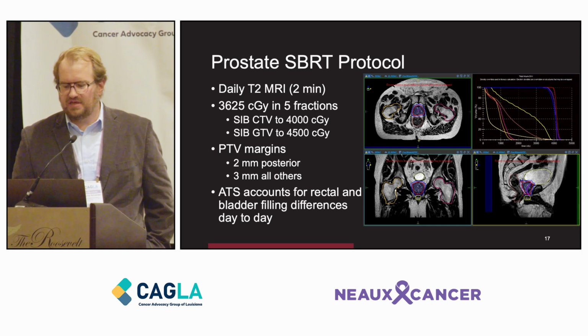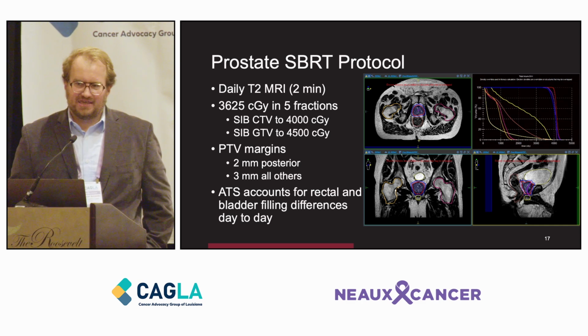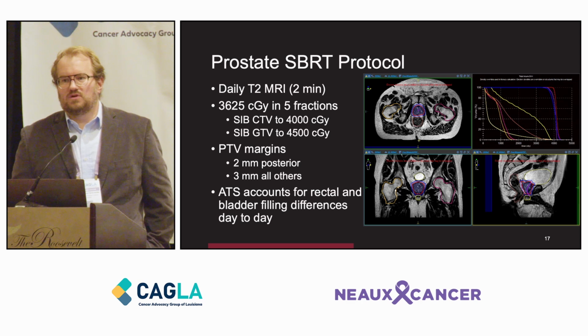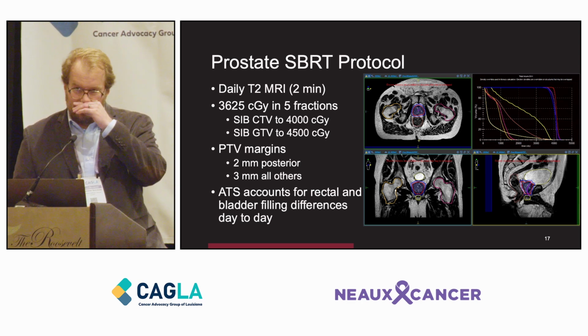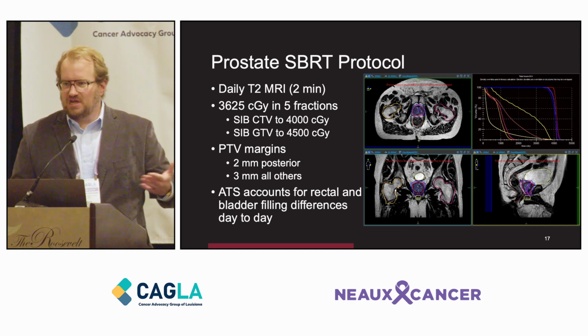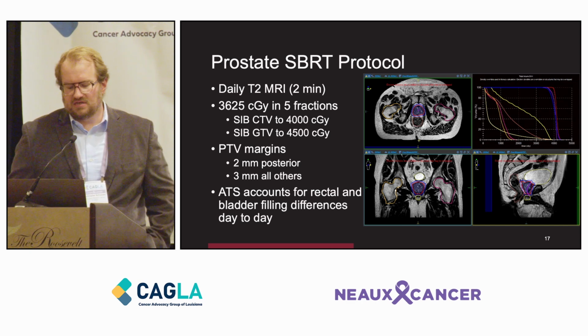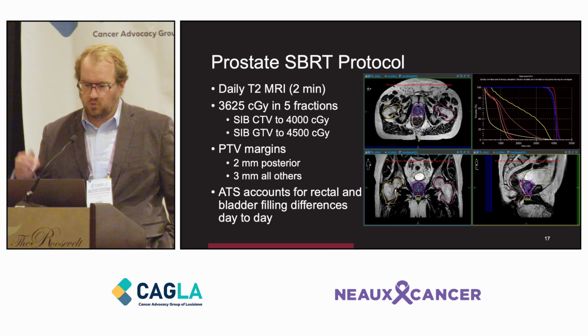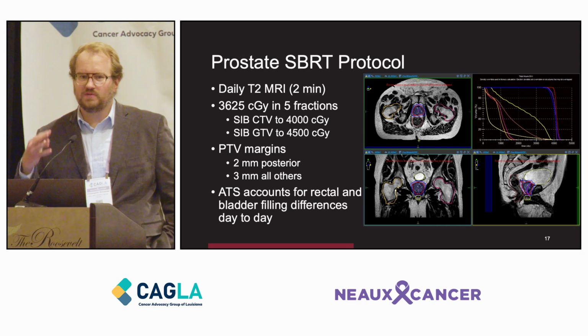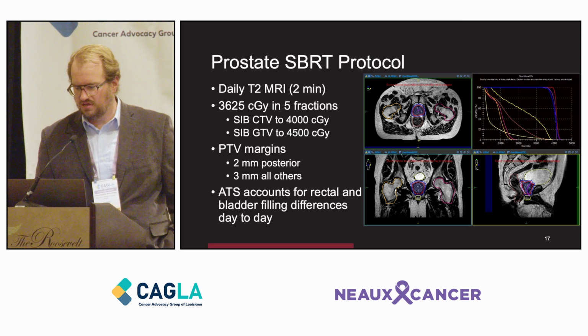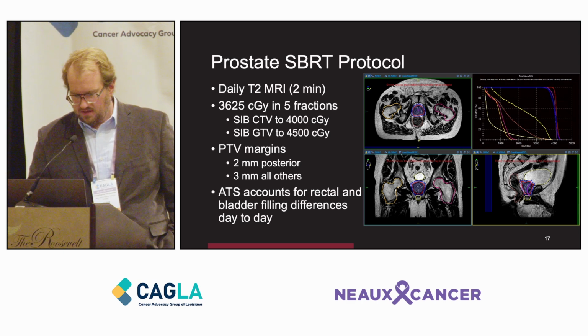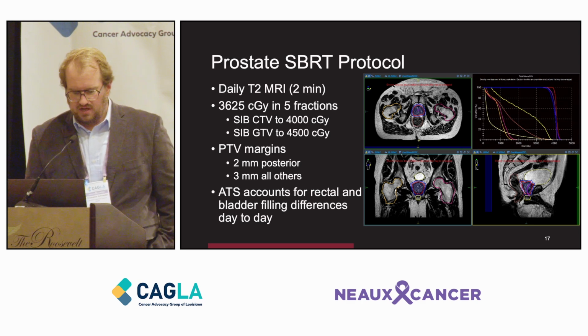We can use that to test the latency of the system, to test the accuracy of the tracking, and, by inserting dosimeters, either an insert where we can put an ion chamber or a piece of film into the target, we can actually do dose measurements to give confidence that the dose is going exactly where we expect it to, and that the beam is shutting off when the target is not in the treatment position. Here is a video showing some of that. You can see the phantom software that is tracking the position of the target in the phantom, and then the live image that we're able to take on the MRI.